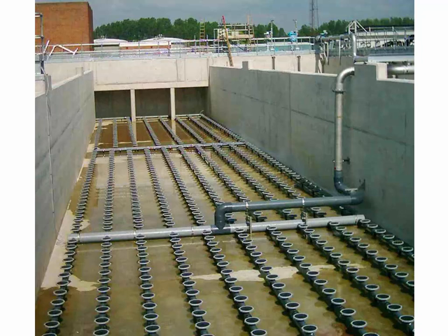So why don't you just close the container from the top so that oxygen stays within the tank? If they're using purified oxygen, they might enclose it. But if it is just atmospheric concentrations of oxygen, then there's no advantage to enclosing the aerator, other than reducing smell. Sometimes in an urban area, they might enclose the entire wastewater treatment process, but putting a roof over this wouldn't enhance the oxygen transfer. But small bubbles will.